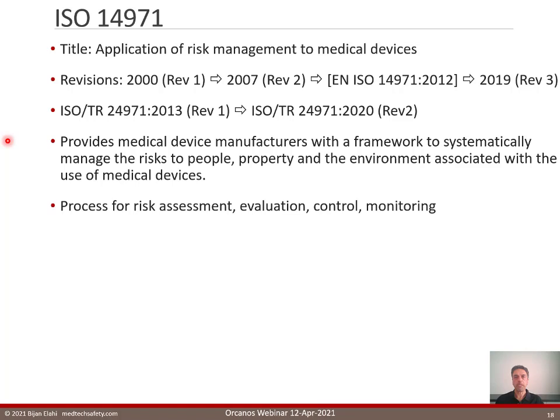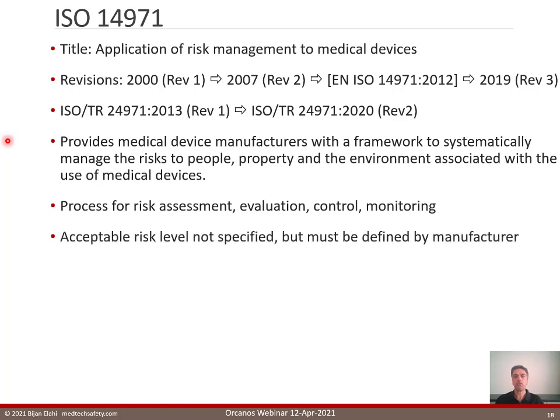It doesn't tell you how to do risk management, but it explains the expectations for doing proper risk management. ISO 14971 expects a process for risk assessment, evaluation, control, and monitoring. The standard does not show you or tell you what is an acceptable risk level. It says that must be defined by the manufacturer. The standard recognizes that management has a great influence on the safety of medical devices, and therefore it bestows a lot of responsibilities on management. For example, that they should assign competent personnel for performing risk management and to define and document a policy for establishing risk acceptability criteria and to periodically review the suitability of the risk management process.